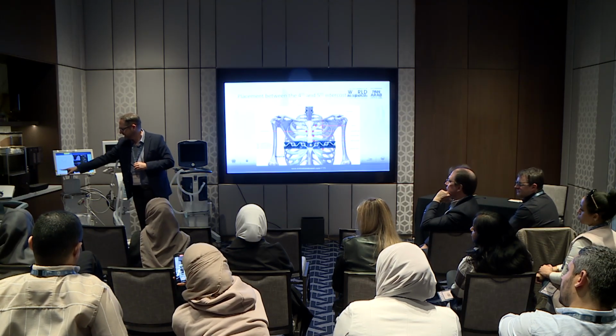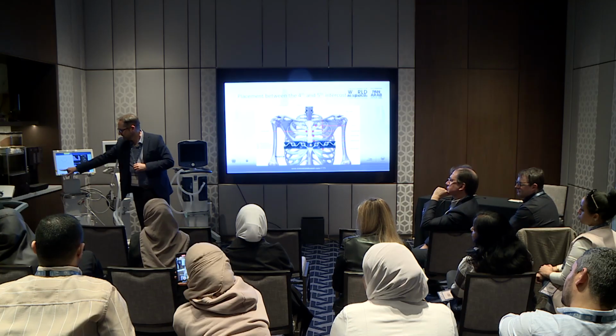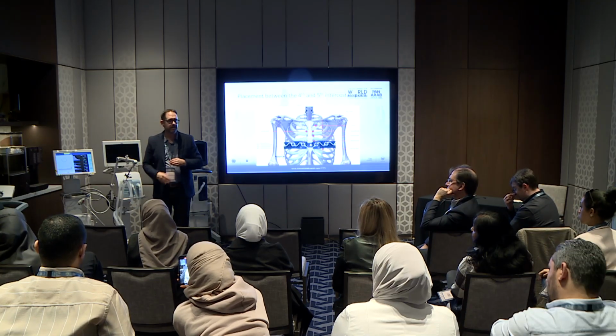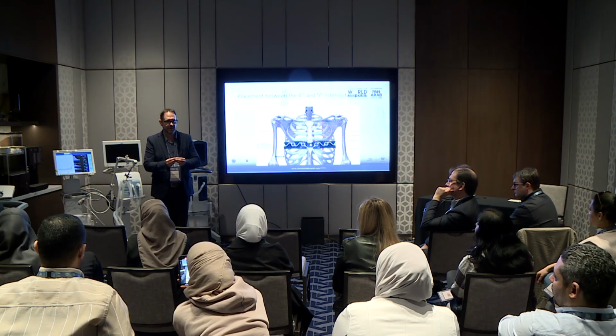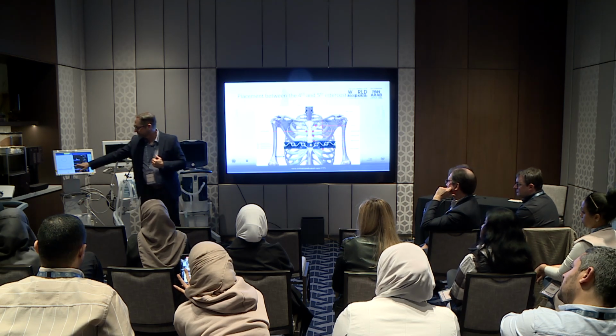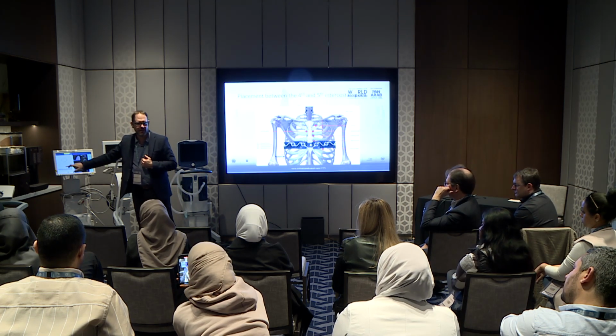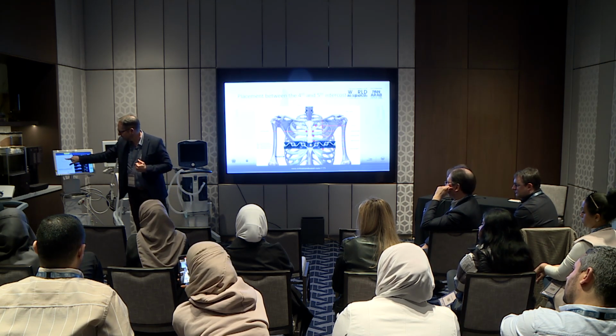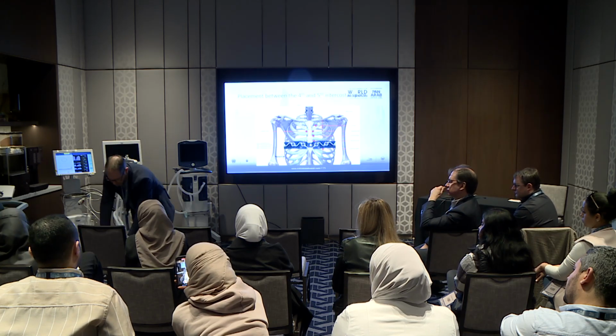When you put this around the patient's chest, all of these leads should be below the red line. What this means is that it has good contact. Okay, so when you put it around the chest, sometimes 1 or 2 leads might be high above the line, and it shows you on the screen which one is which.